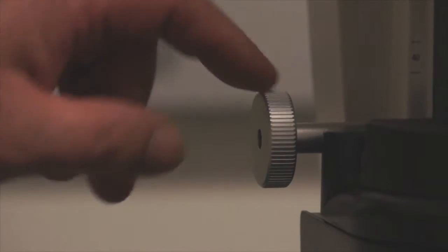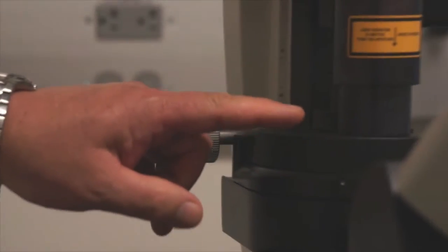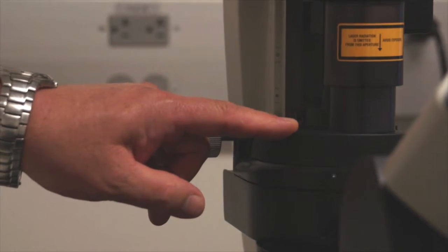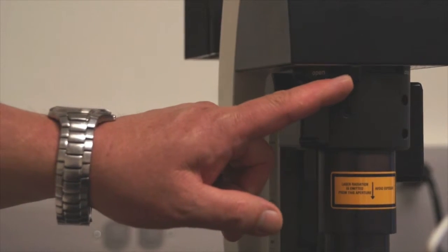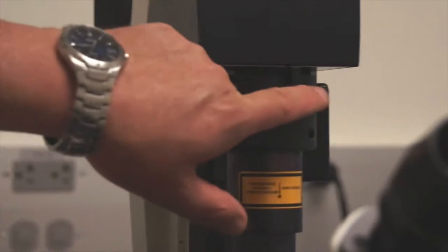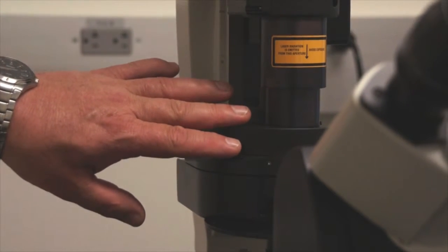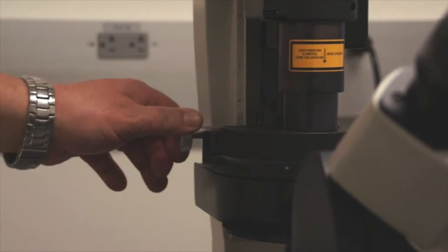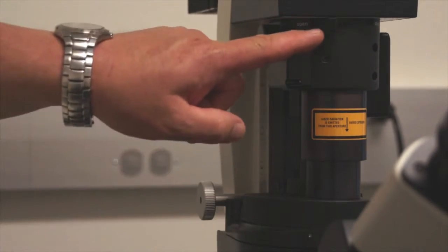This is a knob then that allows us to raise and lower the condenser so that when we align our field diaphragm, it's nice and sharp in the field of view. And so the field diaphragm on this microscope is manual and it's located here. And so we would close this down and open it up so that we could see it in our field of view. And so we're going to discuss condenser alignment specifically as we did on the upright compound microscope, aligning the condenser, closing the field diaphragm, and then using the alignment tools in here to align the field diaphragm to the field of view.